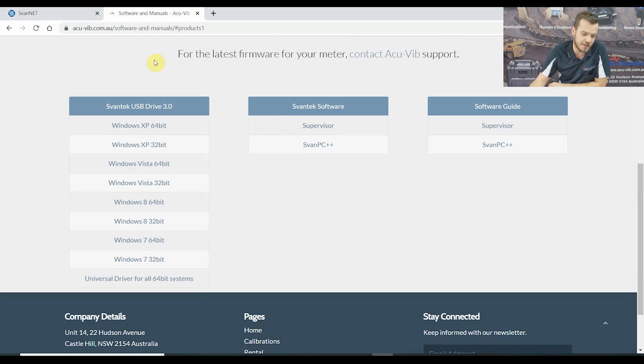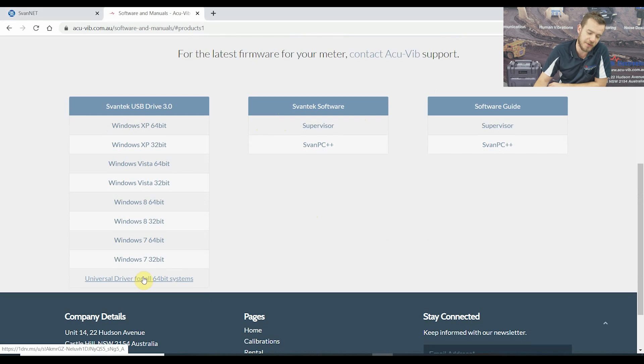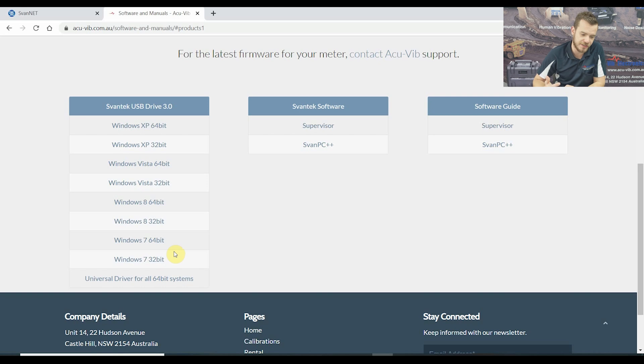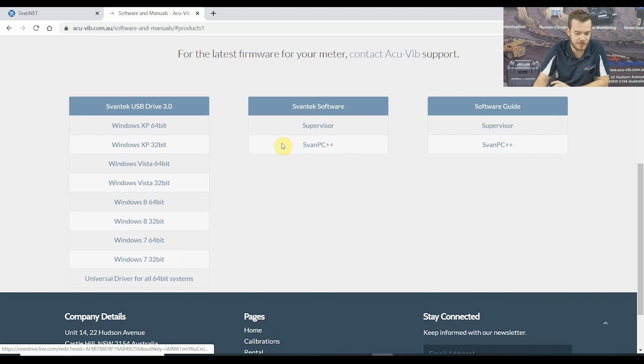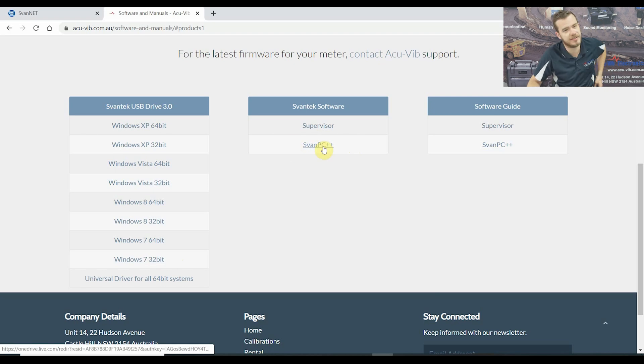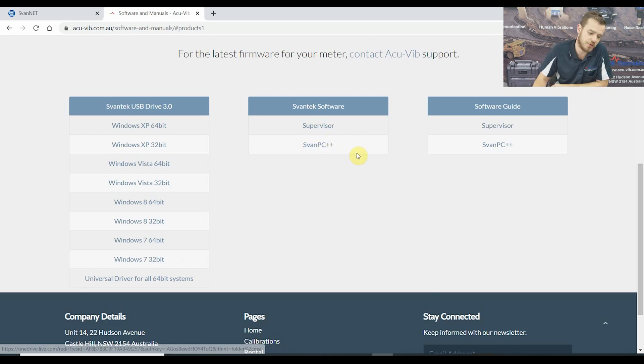If you are connecting the instrument manually via USB, that's where you go to get the USB driver for your system and install it. If you have trouble connecting the instrument, you might have to disable firewall protection. If you're just downloading data through the web interface, all you need is the SvanPC++ software. Download it — it'll take you to a OneDrive link — install the software, and it should save to your desktop.